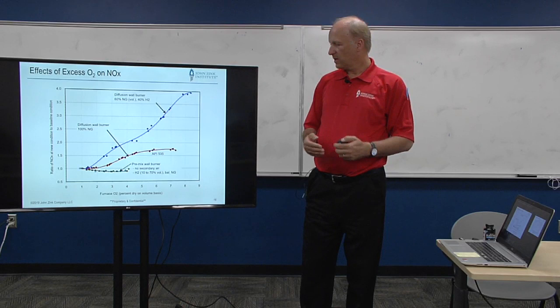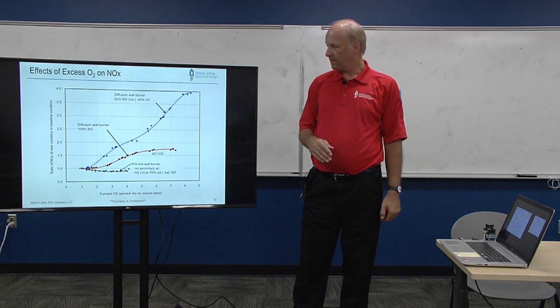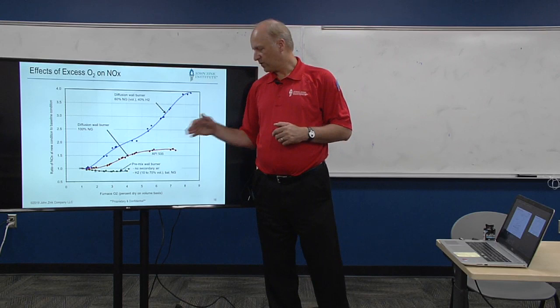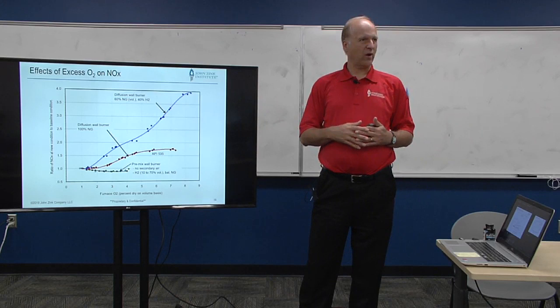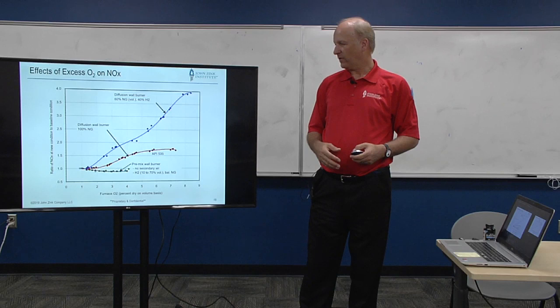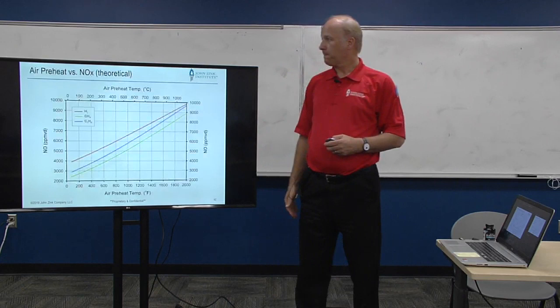This is a curve from API Standard 535 showing excess air or excess O2 effects on NOx. The main point is that API has a generic curve in their standard, but real burners could be worse or better than that — so be careful about using a generic curve, as it's very dependent on conditions and the kind of burner you have.